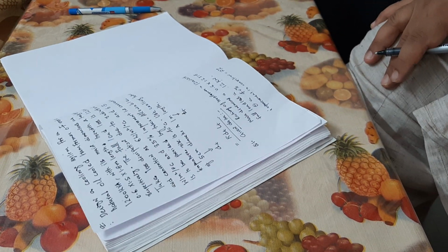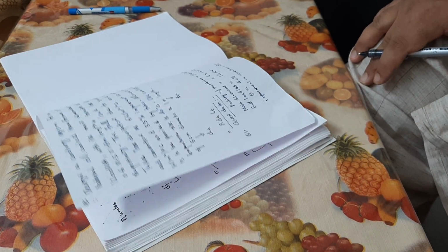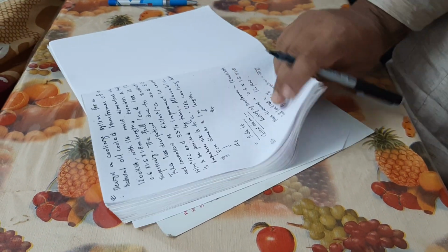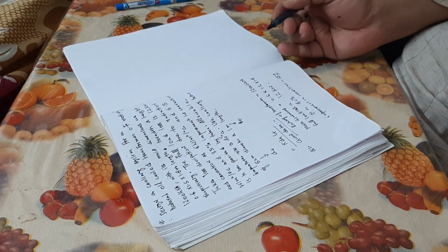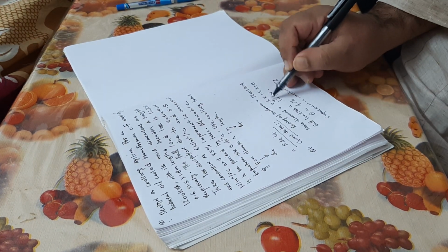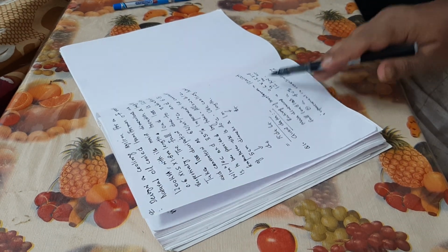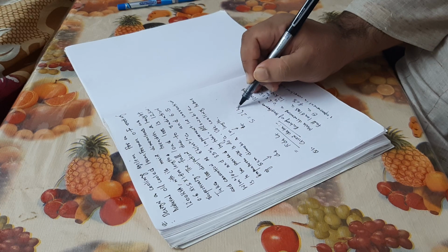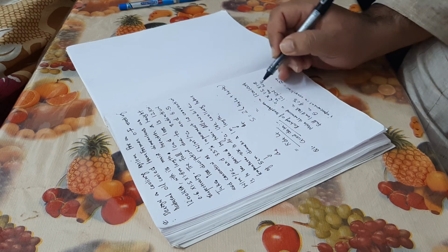So how do we go about the problem? The first thing we are interested in is to calculate the total heat dissipating surface. First of all we have to see what is what. Here you see this is your LT, this is your HT, and this is your WT. So the total heat dissipating surface S would be twice HT·LT plus HT·WT.